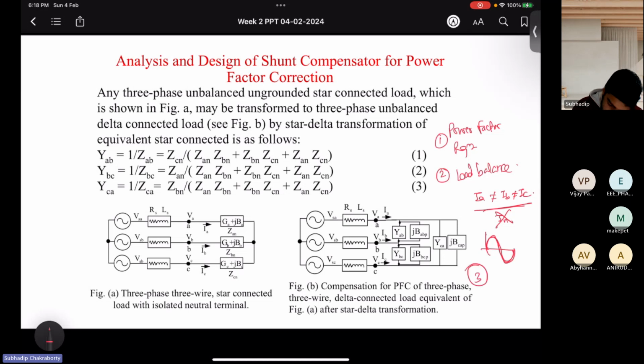And the third case is ZVR, zero voltage regulation. You can do this too, but note these two are not possible at a time. You can do either one, because the philosophy is to regulate the voltage, or a priority. Which one are you giving priority? In remote areas, voltage regulation is more of a priority than power factor, because very little load is connected at the remote areas. Voltage regulation is still a challenge there, and that's why ZVR may be preferred in those areas, and it has a different philosophy.